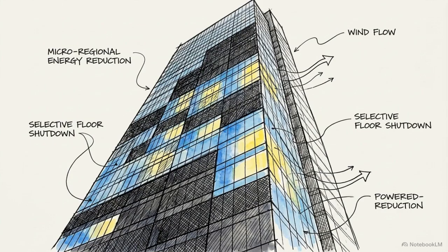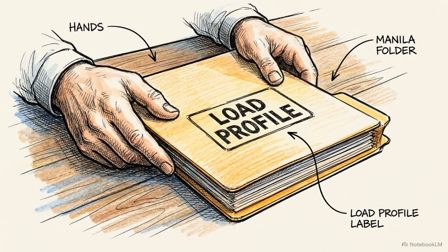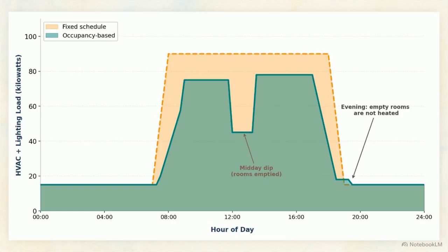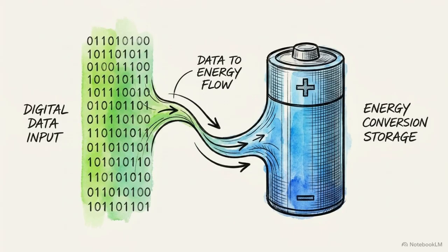Let's transition from theory to empirical data and examine the specific daily load profile of an office building. This chart plots energy load over 24 hours. The orange dashed line represents a fixed schedule, blindly burning 90 kilowatts all day. The green occupancy-based line dynamically follows human arrival and plunges during midday. The gap between them represents the exact carbon and capital saved. The reduction shown in this shaded region is the direct result of using information to replace waste.